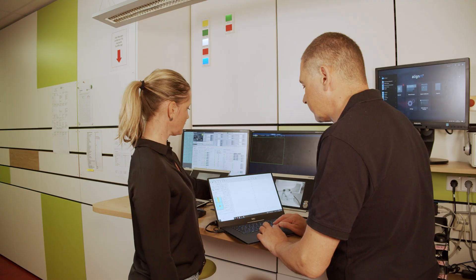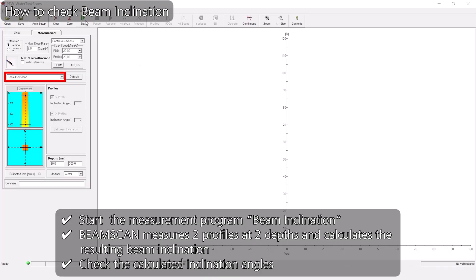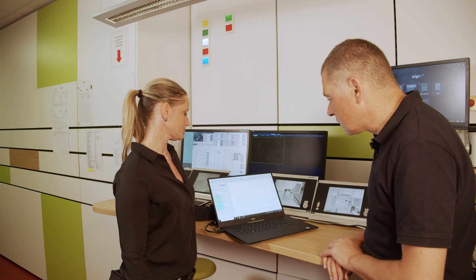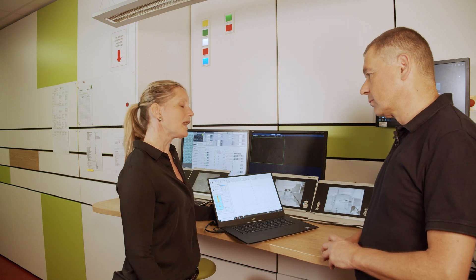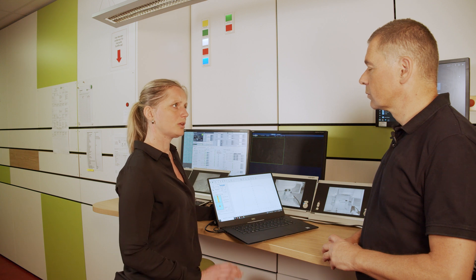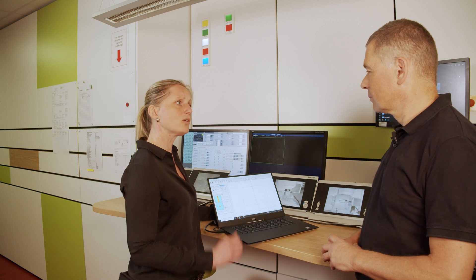Okay, let's start the beam inclination. Impressive. The auto setup is really cool. What else can BeamScan do for me? BeamScan is a really sophisticated system. It can determine and correct your beam inclination. It can save your valuable measurement time by using artificial intelligence. And it can check your measurement directly during the measurement.